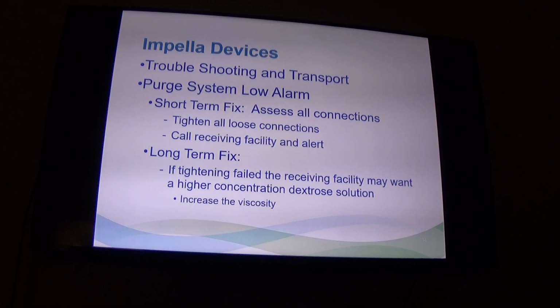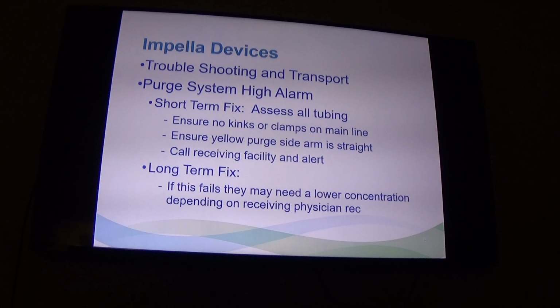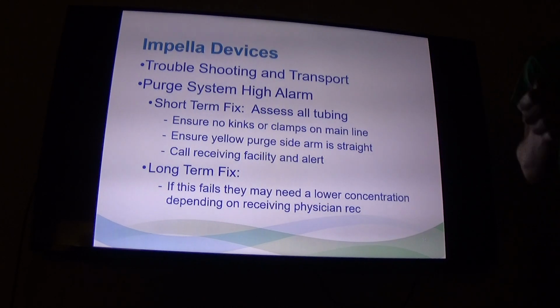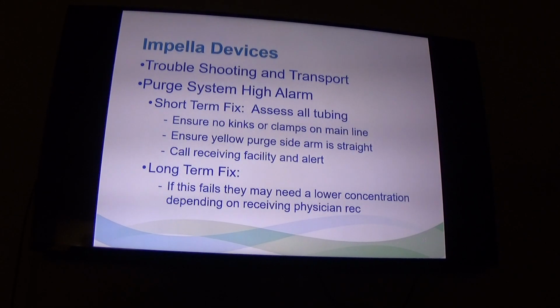The device is made to go from D5 in water all the way up to D40, so pretty high viscosities. If you get a purge system high alarm, this is the more common one of the two, and usually you've moved the patient and the line has become kinked. All you need to do is ensure that all those lines are nice and straight.